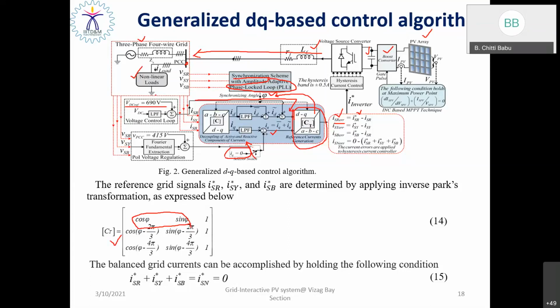When the grid is under balanced condition, obviously we know we use a 3-phase 4-wire system to power both single phase as well as 3-phase loads. Then the neutral current is 0 when the grid is under balanced condition. But whenever the grid is unbalanced, then the neutral current is not 0, and hence the circulation of the neutral current causes third harmonic current to be generated in the grid. And again there is a problem associated with losses in the transmission system, including the interfacing inductor and transformer as well.